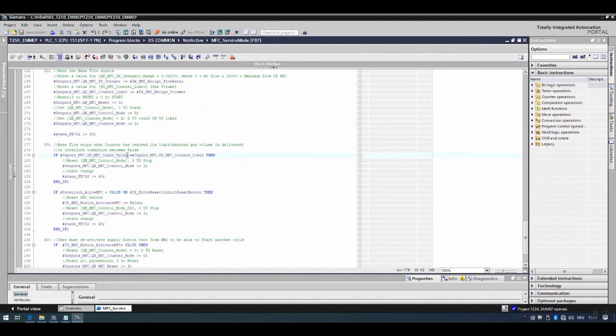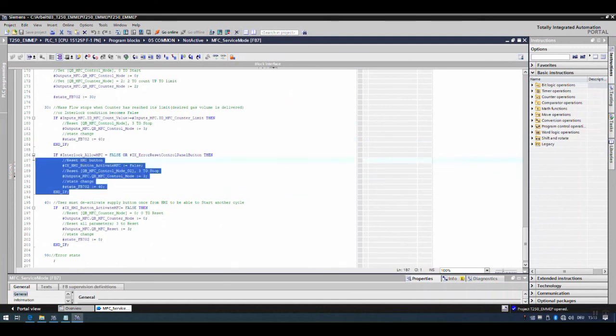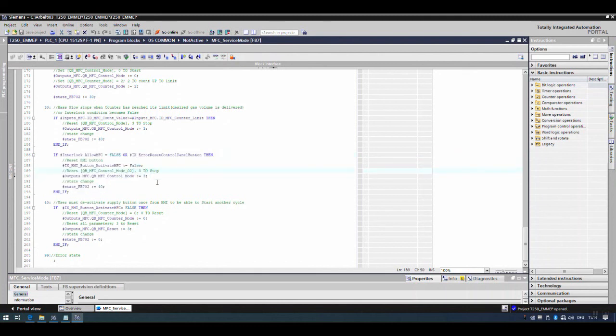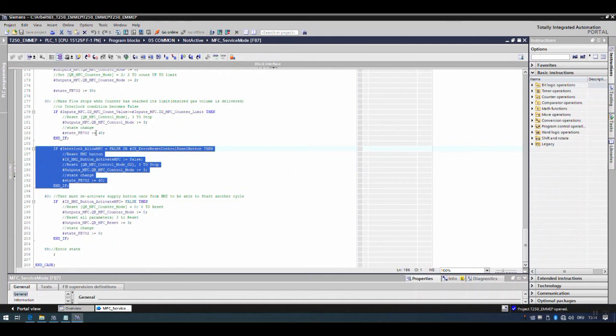In the second state, we read inputs from the MFC to the PLC. When the MFC reaches the counter limit, we stop the MFC by setting control mode to 3, then move to state 40. If something goes wrong — no gas in the line, low input pressure, a closed post-MFC valve — the MFC generates an error. If an error occurs or a solenoid closes during the process, we can change state to an error state or simply close the MFC.